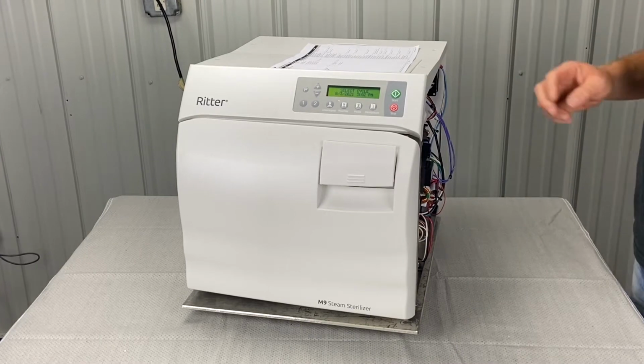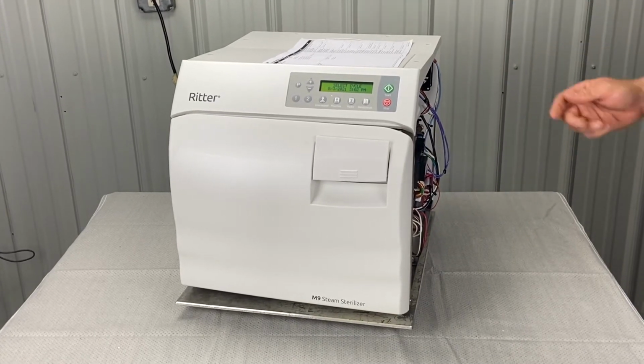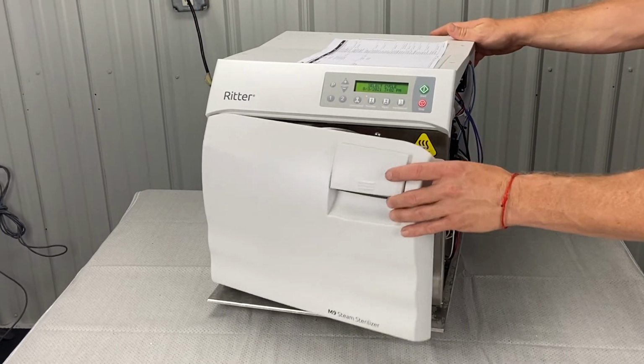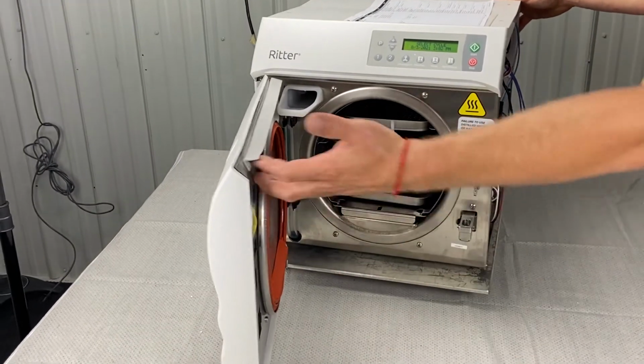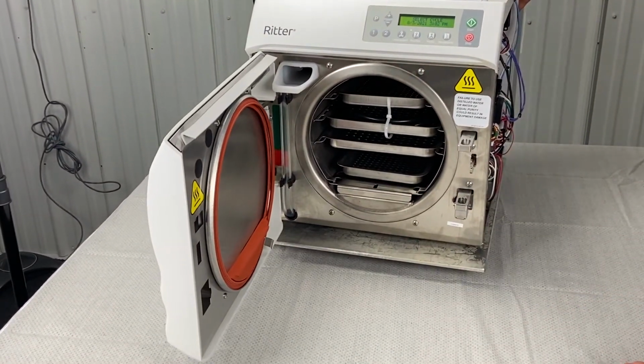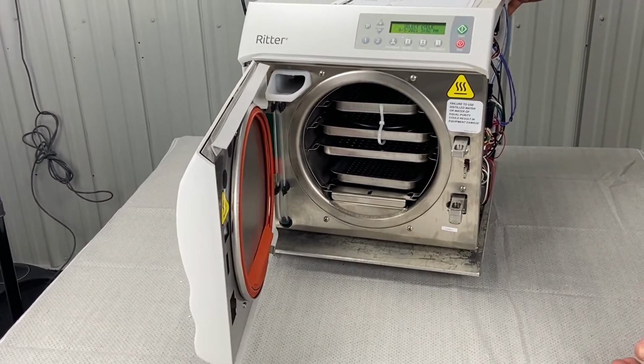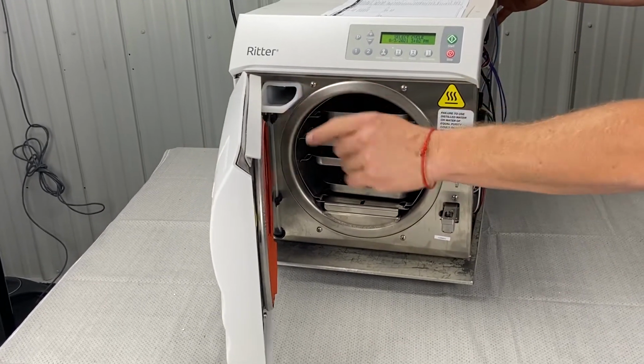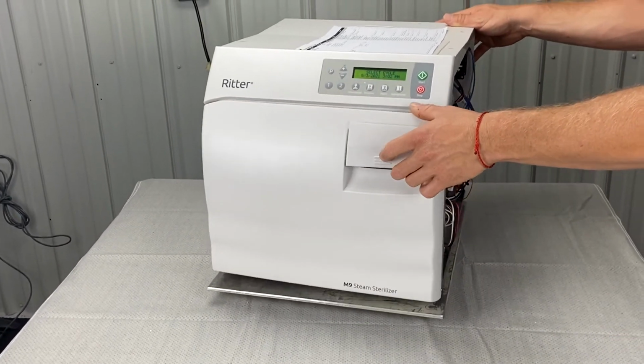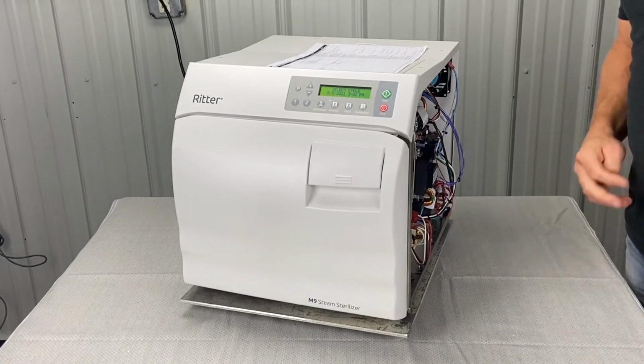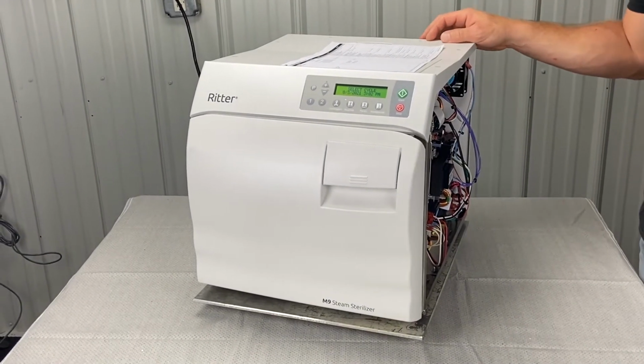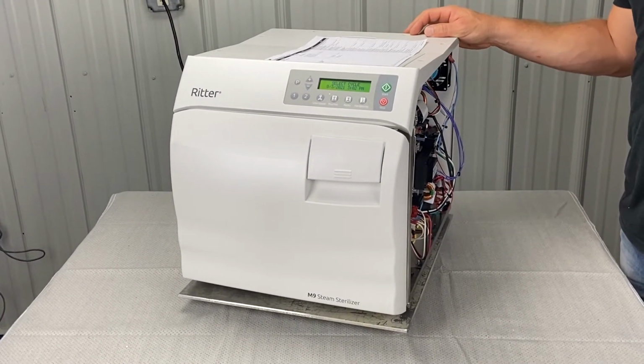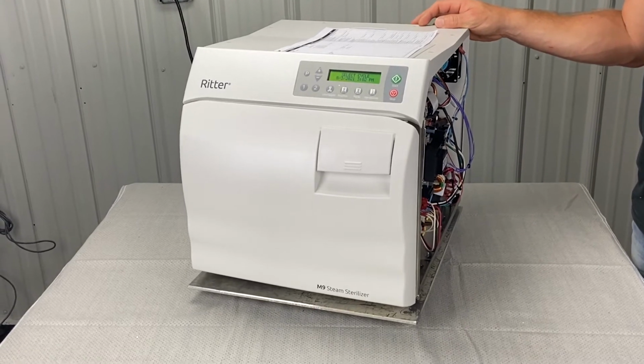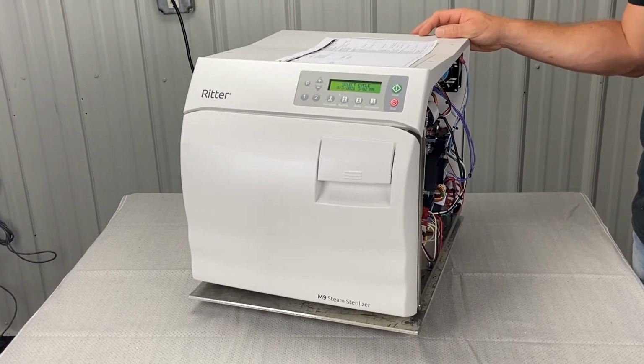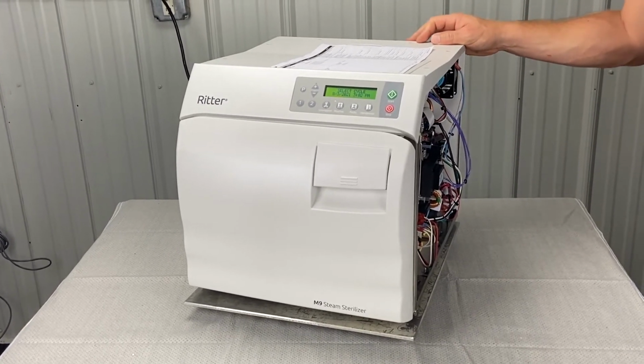Replace gasket kit 1 time a year. Again, that's depending on cycle usage. If you're using these things 10 cycles a day, you're running them back to back, you're loading tons of instruments in it, that is not going to last you a year. So, leaking or defective air valve. Check for excessive steam coming through condensation coil spout. During the heat and vent modes, it is normal for steam to be exhausting through the spout.